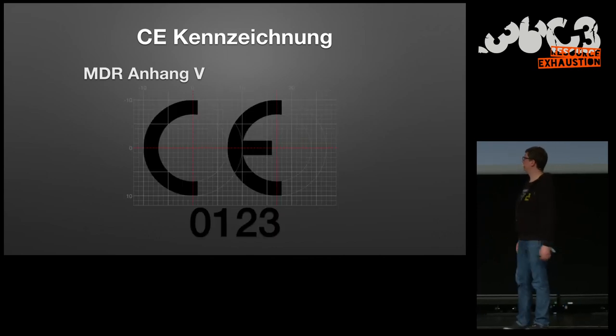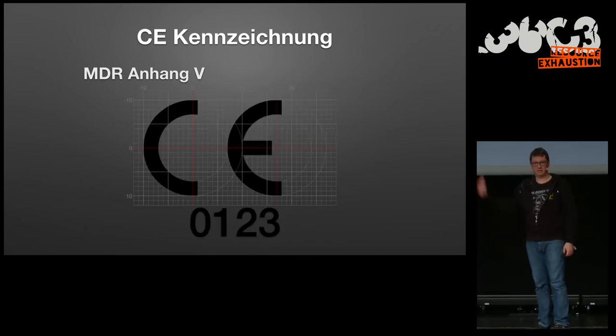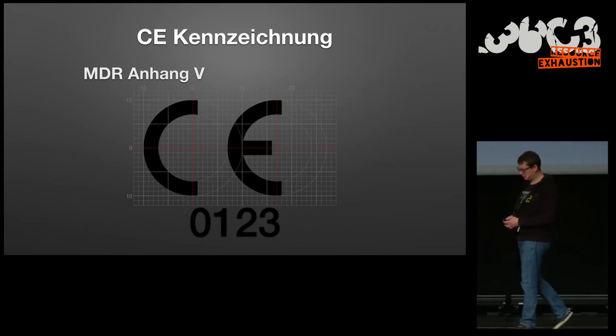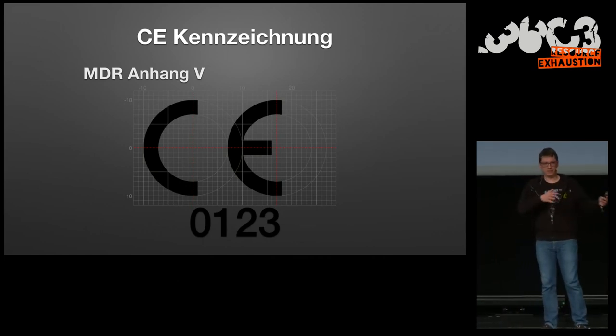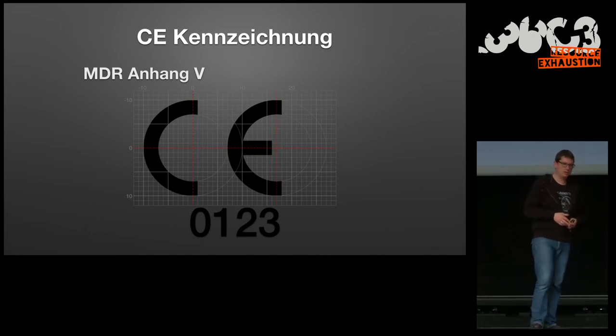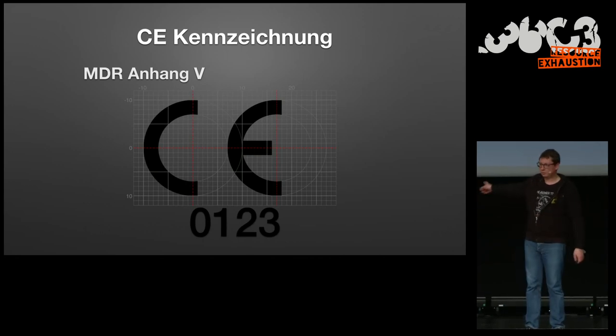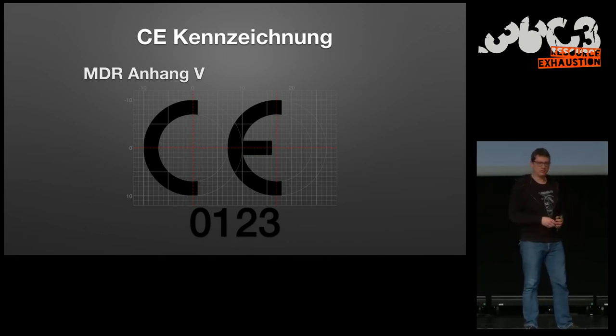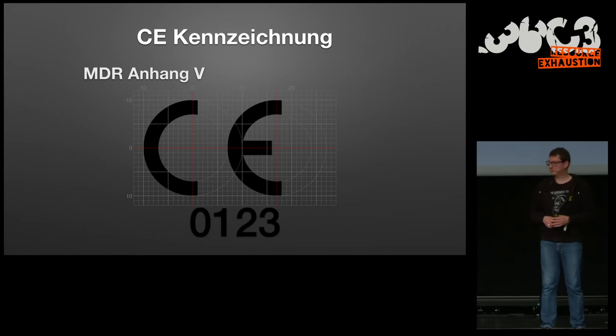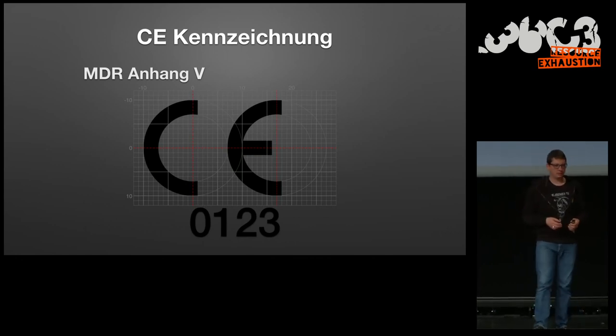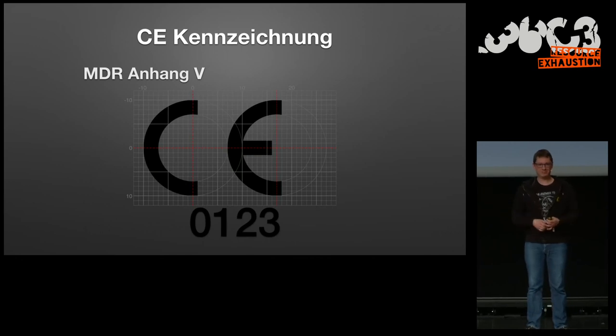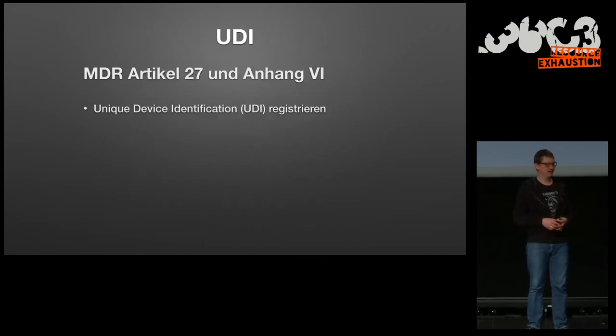If this is done, that's great. Then in Annex 5 you get a CE certificate, which means exactly that you have declared the conformity, that it is safe according to the notified body and the manufacturer, and underneath you have the number of the notified body. In this case, 0123. Depending on where you go, you might have a different number there.